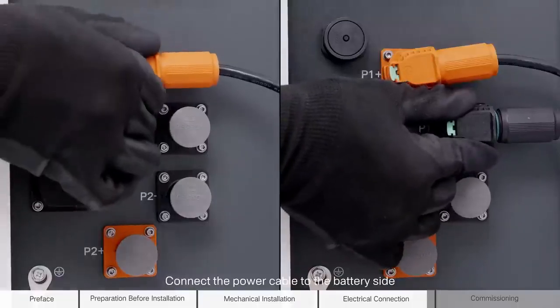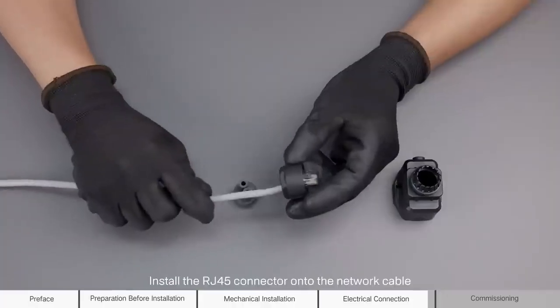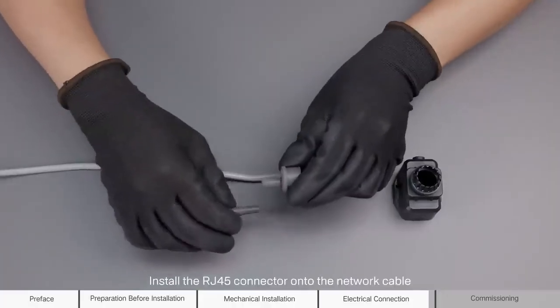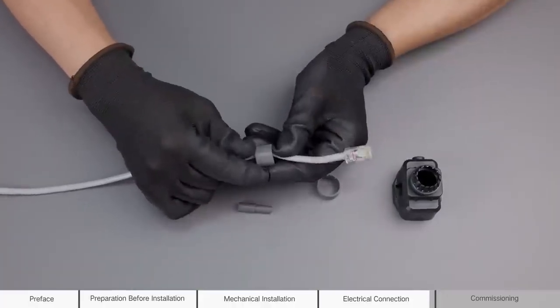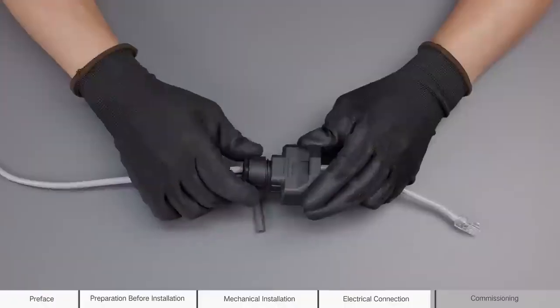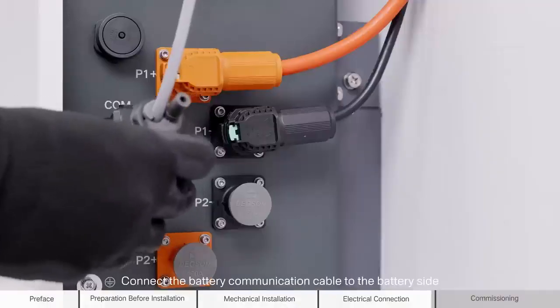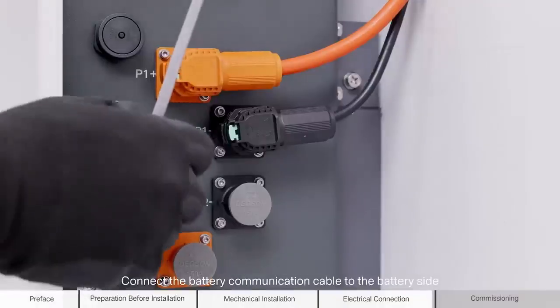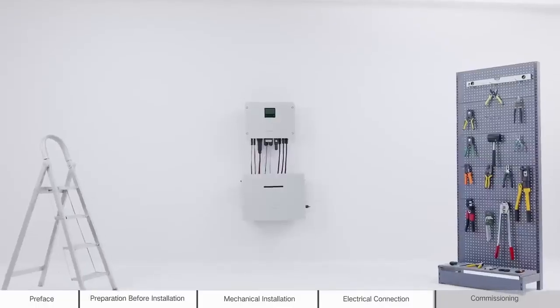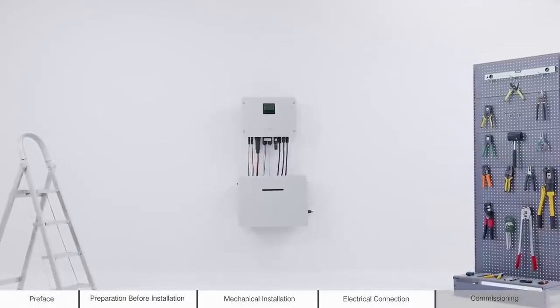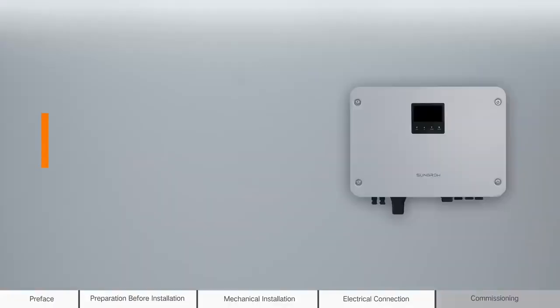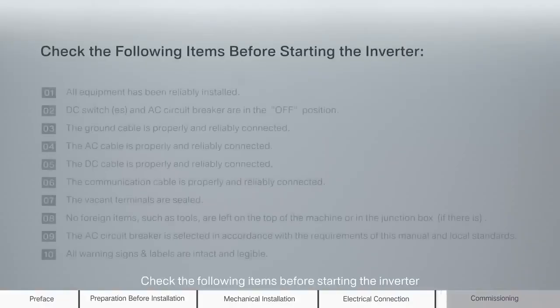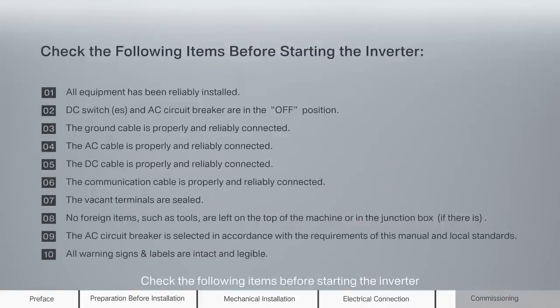Connect the power cable to the battery side. Install the RJ45 connector onto the network cable. Connect the battery communication cable to the battery side. Step 4. Commissioning. Check the following items before starting the inverter.